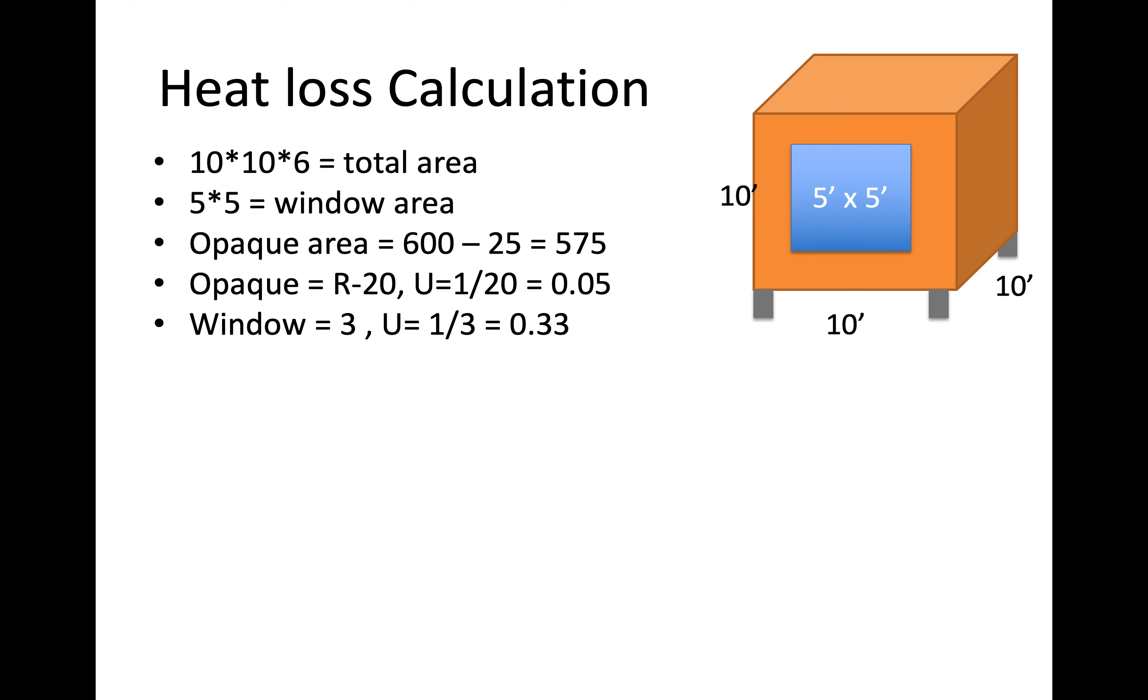And then the r values of each characteristic is also important so the opaque areas are r20 so to find the u factor, because we can't average R-values just area weighted u factors, is going to be the reciprocal so 1 over 20 equals 0.05. So that's our u factor for the opaque areas and then the window, we know it's an r3 window, so 1 over 3, that's 0.33 for our u factor there.